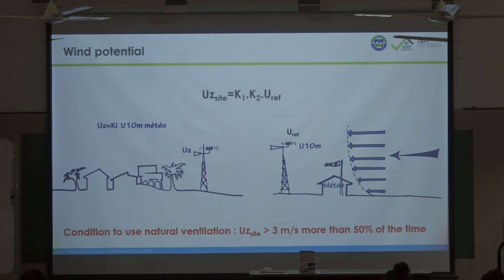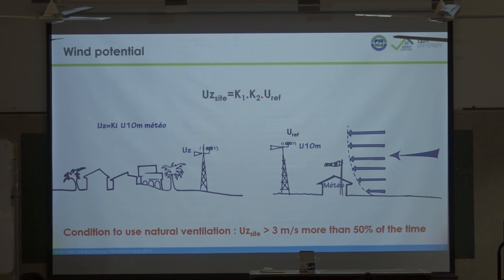The issue is that you need a mast and to record data at a height of 10 meters. If you cannot afford a weather station or don't have time to install one, you can use correction coefficients k1 and k2, which depend on the roughness and topography of the site. You then check the condition for natural ventilation: the mean air velocity must be above 3 meters per second more than 50 percent of the time.